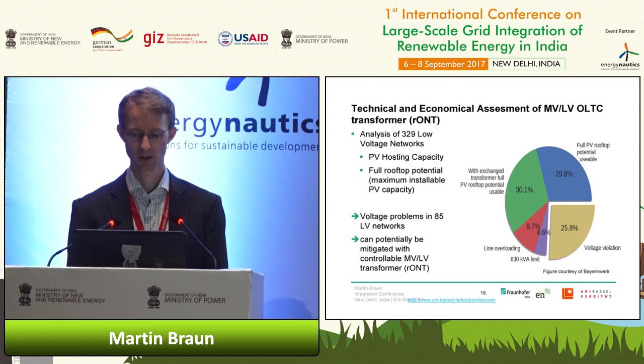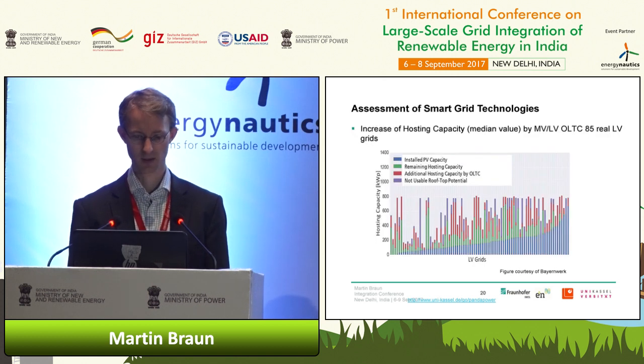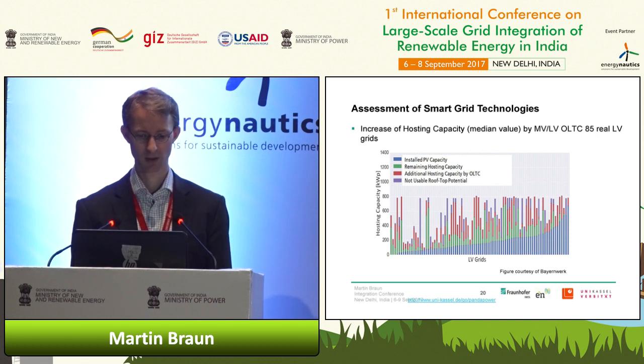We consider that quarter of the grids in more detail, analyzing them as distributed here. Next to the already installed PV capacity, some grids already have a very high installed capacity, for example 800 kilowatts. We can see in green the remaining hosting capacity, and by installing an on-load tap changing transformer, shown in red, we can increase that further.